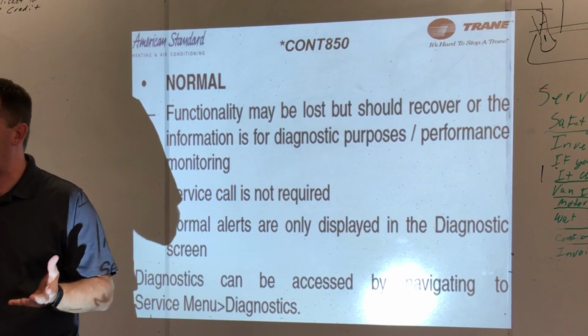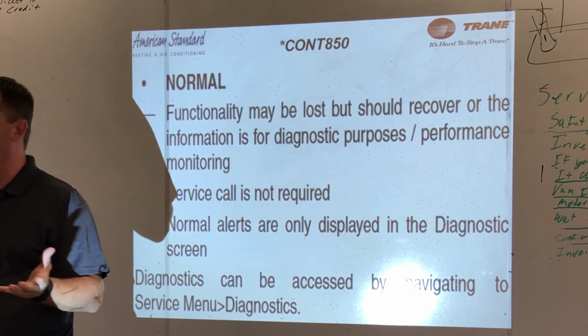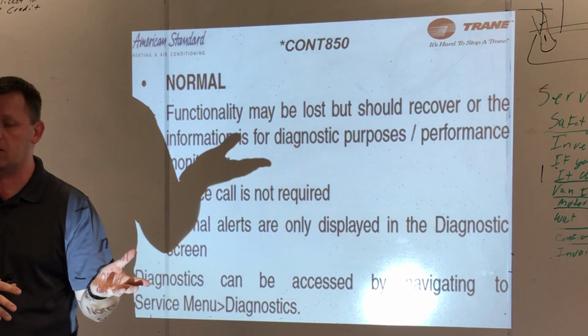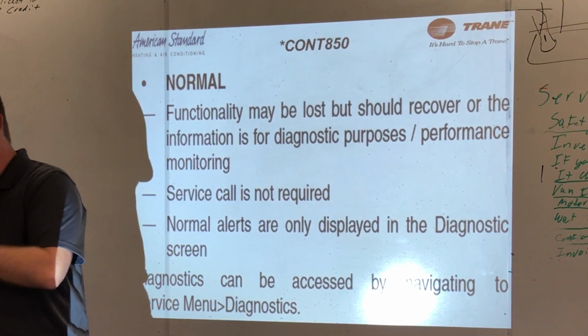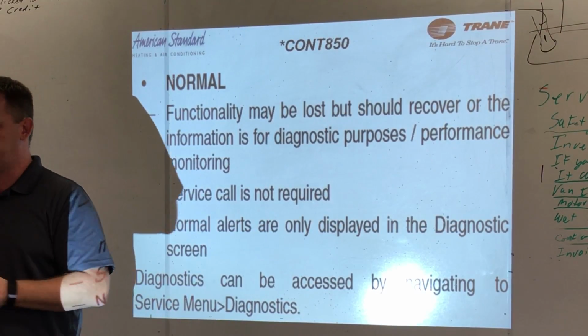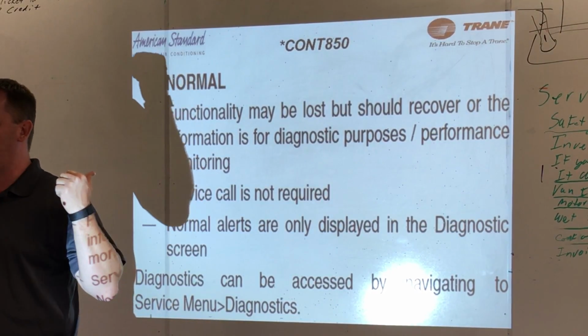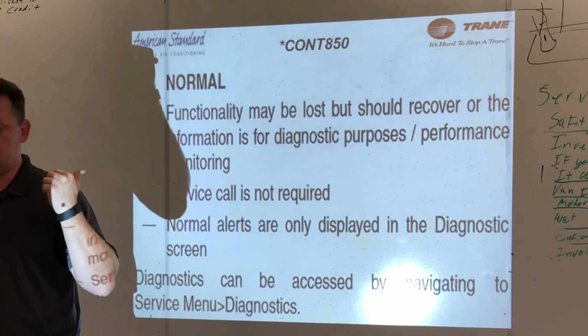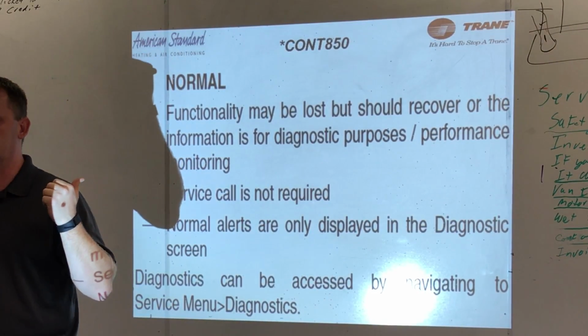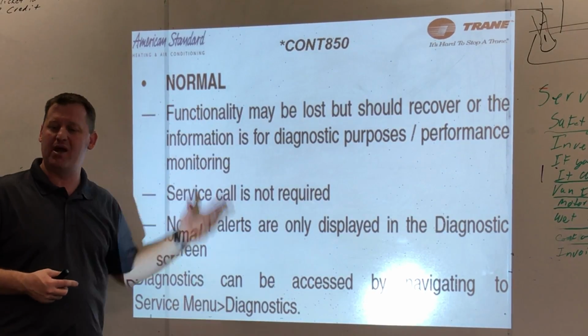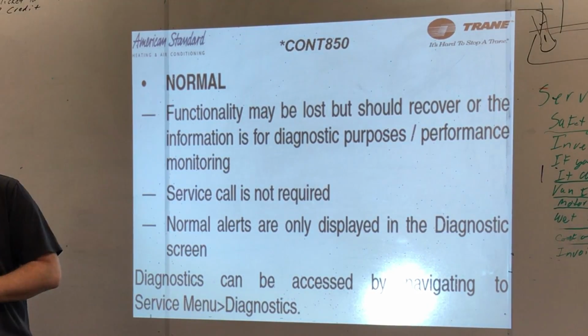And so this type of alert would be what we'd consider a quote unquote normal alert that's going to happen periodically. Now, if it's 90 degrees outside and 75 in the house, and we're getting indoor coil frost protection, okay, maybe we need to dig into that one, right? Because we shouldn't be having frost protection. So normal alerts may or may not need more checks.